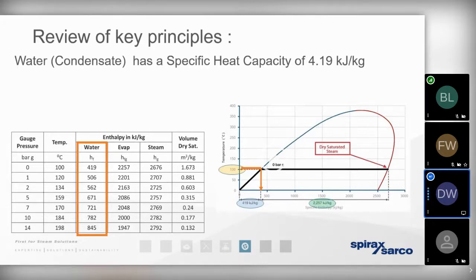If we're boiling the water at zero bar gauge, where the boiling temperature is 100 degrees, we need to add 419 kilojoules of energy to it. We refer to that as the enthalpy of water. We can refer to it as the sensible heat. That doesn't give us steam, it gives us boiling water.